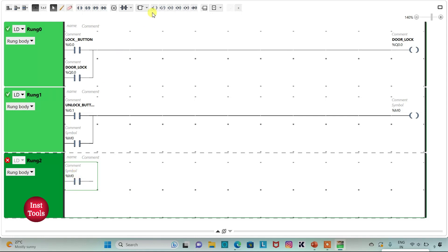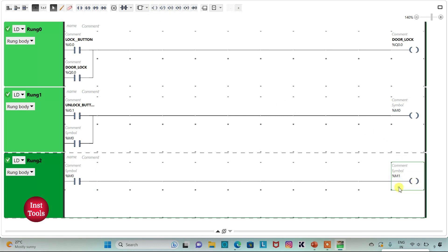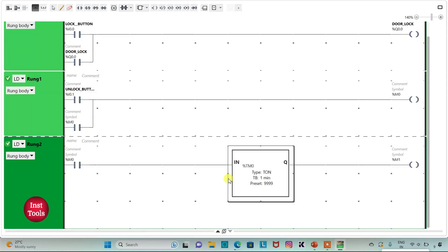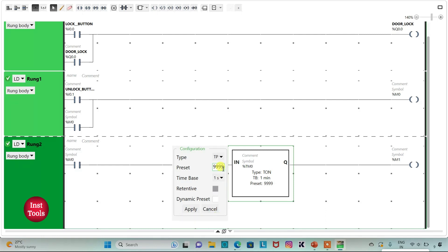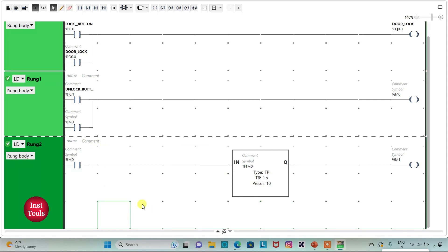I will insert a coil with address M1, and for M1 I will use a timer of type TP. I will change the time base to 1 second and preset value to 10. So when the unlock button is pressed and released, M0 gets activated, and when M0 gets activated, M1 gets activated for 10 seconds.